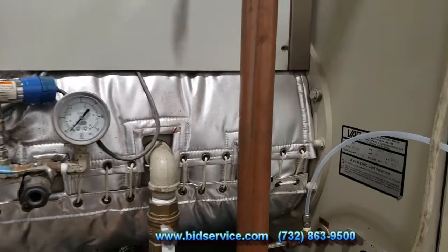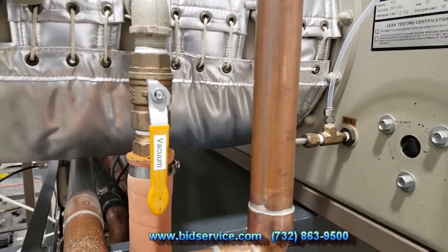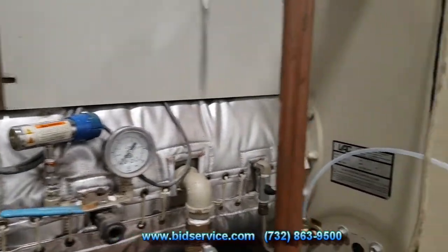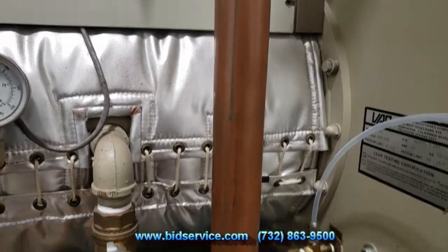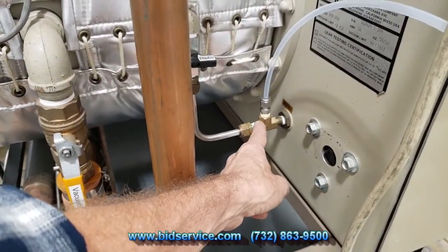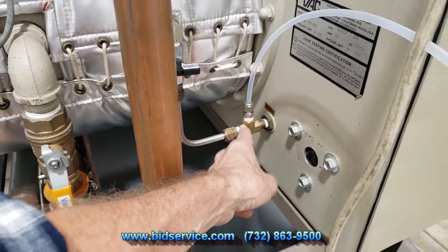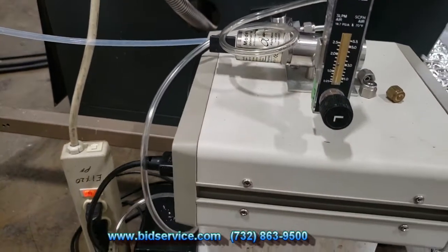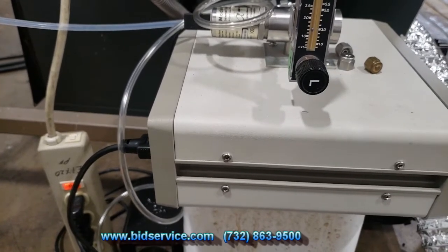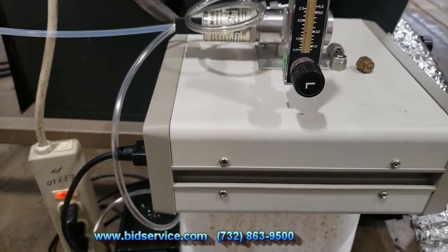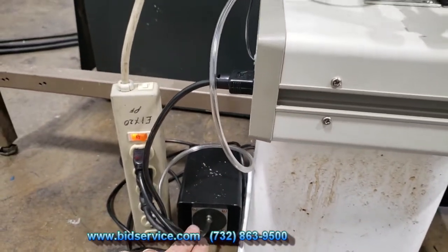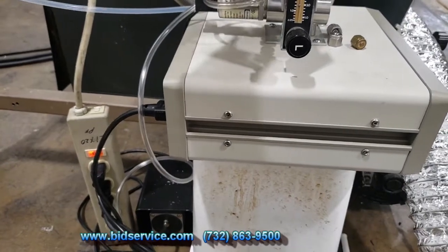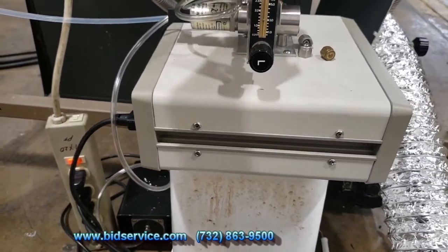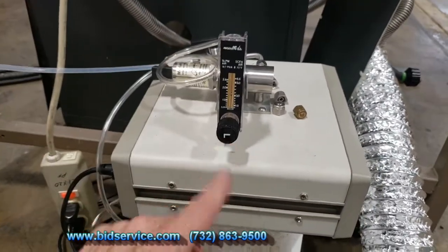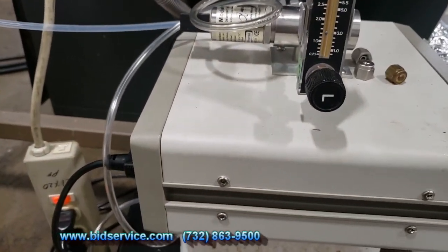Okay, one other thing I want to point out while we're here is we do have a vacuum line coming in. We're only using one pump on this system. And the other thing to point out is I'm sampling the moisture inside the box, and I'm bringing it through this line here, which then goes to this house setup. This is what we typically use to qualify the machine, the glove box, to verify that it does reach 1 part per million. And we have a little diaphragm pump down here pulling the gas from the box across the sensor, which is right here, through a flow meter, and it's set at 1.5 liters per minute.